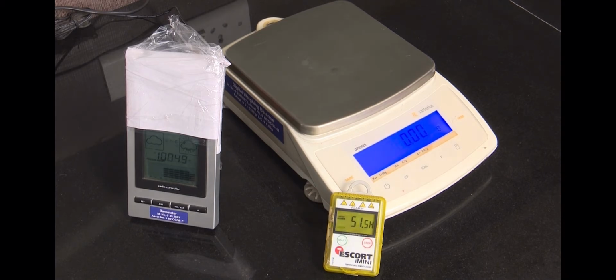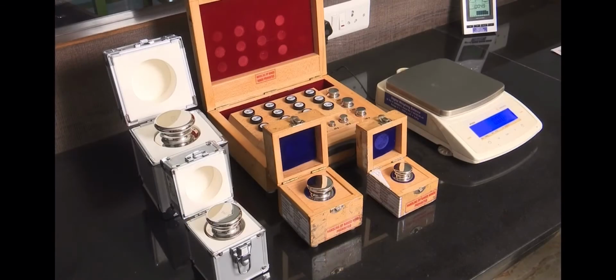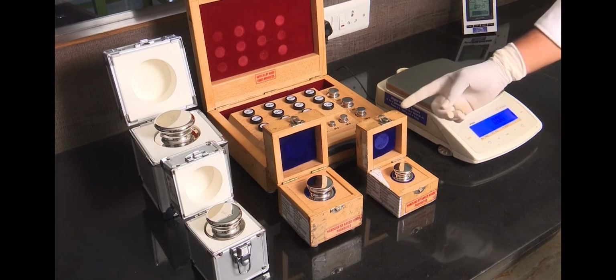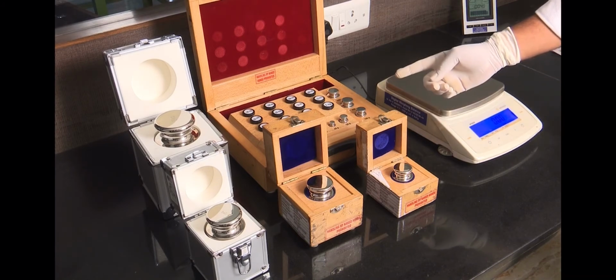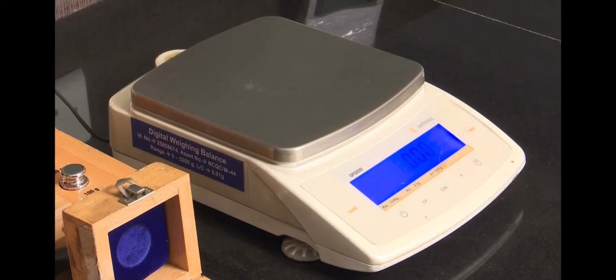Before starting calibration, ensure that the environment condition is maintained. The temperature should be 23 plus minus 0.5 degrees Celsius. Barometric pressure is 1000 plus minus 15 HPa and humidity should be 40 to 60% RH. For calibration, we will use weights as reference instruments. I will calibrate the weighing balance for 3 tests, namely linearity test, eccentricity test and repeatability test.